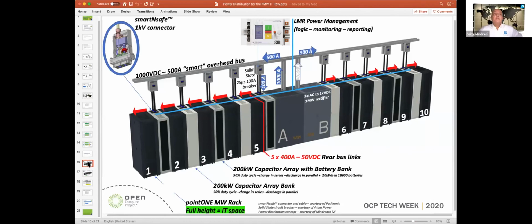One thing I'd like to mention is fault current, because a good point was made about 18,000 amps of fault current that may happen with a conventional breaker. With solid state breaker technology, that would be reduced significantly should the fault occur beyond the breaker in the distribution segment, because the reactive speed is much higher, so you can preset the breaker to quickly turn off at any given value.